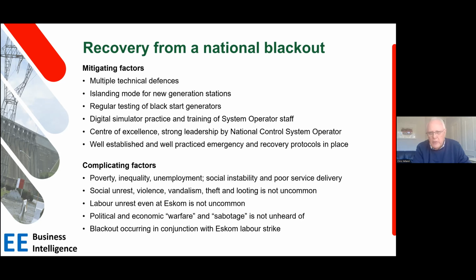From a cold power station, recovering to full output can take several days. However, if you can keep the power station and boilers ticking over, recovery can be within an hour or two. So islanding mode on some of the power stations is very useful - not the older ones, they can't do this, but the new ones are designed with islanding mode as part of their operation modes. That's very helpful when the whole country is in a blackout, because you need certain power stations able to restart quickly so you can restart the whole power system from scratch.